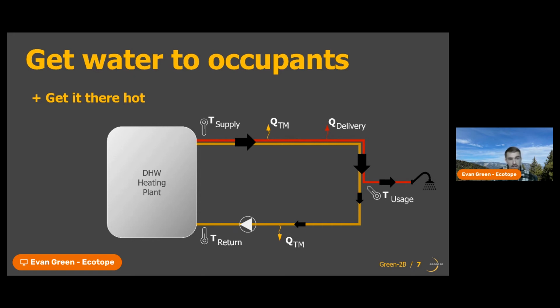So this works really well as long as this water is moving and it's actually being delivered to a fixture. But as soon as someone turns that fixture off or they're not in use, then this water is going to sit in the pipe and it's going to cool down even further. So then as soon as someone needs to turn on that fixture and access that hot water, they're going to have to flush all of that cooled water out of the pipe before they can actually have access to the hot water from the plant. So to counteract that, we're going to install this temperature maintenance loop that's going to continuously circulate water, so then we always have fresh hot water available whenever someone opens that tap.